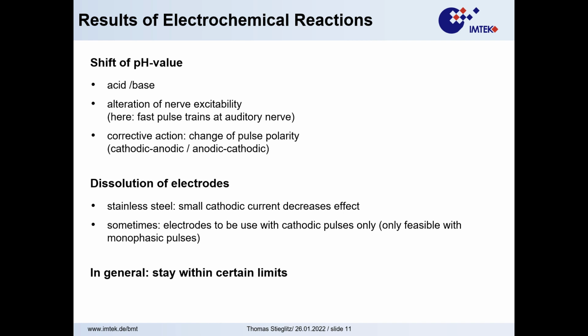One measurement method that has been established is that you stimulate electrodes in vitro in beakers in salt water, billions of times, and then you investigate the water. Not only the electrode, but you investigate the water to see if there are solvents in there. Since the detection limit of most of the machines is above the amount of platinum that might have been dissolved, you play some tricks, so you evaporate the water: I have now 10 milliliters, I cook that down to 1 milliliter, that's a factor of 10, and I go to whatever mass spectrometer. If I find platinum, then I have to divide that concentration by a factor of 10, and then you can find that out. That's established worldwide as a method to check, do I have dissolution or not.